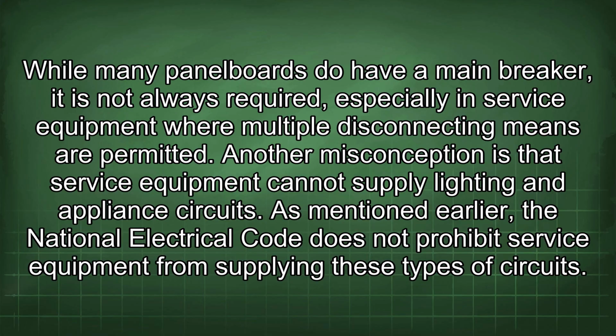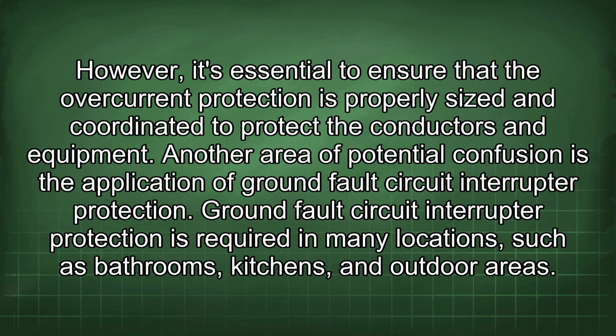As mentioned earlier, the National Electrical Code does not prohibit service equipment from supplying these types of circuits. However, it's essential to ensure that the overcurrent protection is properly sized and coordinated to protect the conductors and equipment. Another area of potential confusion is the application of ground fault circuit interrupter protection. Ground fault circuit interrupter protection is required in many locations such as bathrooms, kitchens, and outdoor areas.